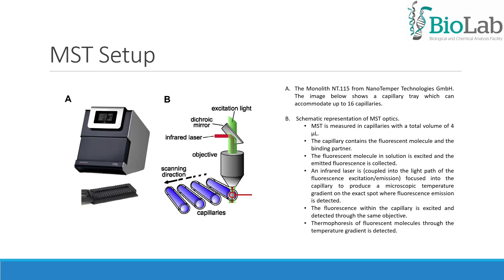This is the overall setup of the MST optics. MST is measured in capillaries with a total volume of 4 µL. The capillary contains the fluorescent molecule and the binding partner. The fluorescent molecule in solution is excited and the emitted fluorescence is collected. An infrared laser coupled into the light path of the fluorescent excitation emission is focused into the capillary to produce a microscopic temperature gradient on the exact spot where fluorescence emission is detected.